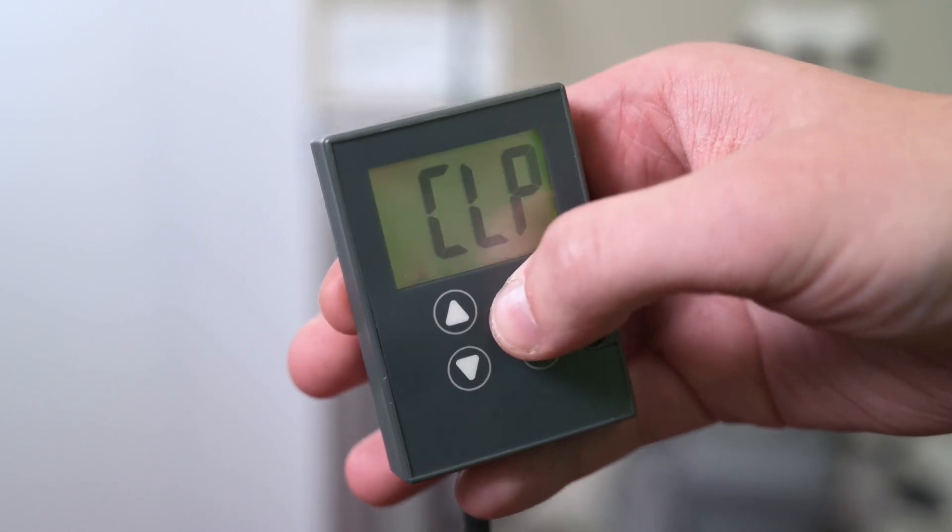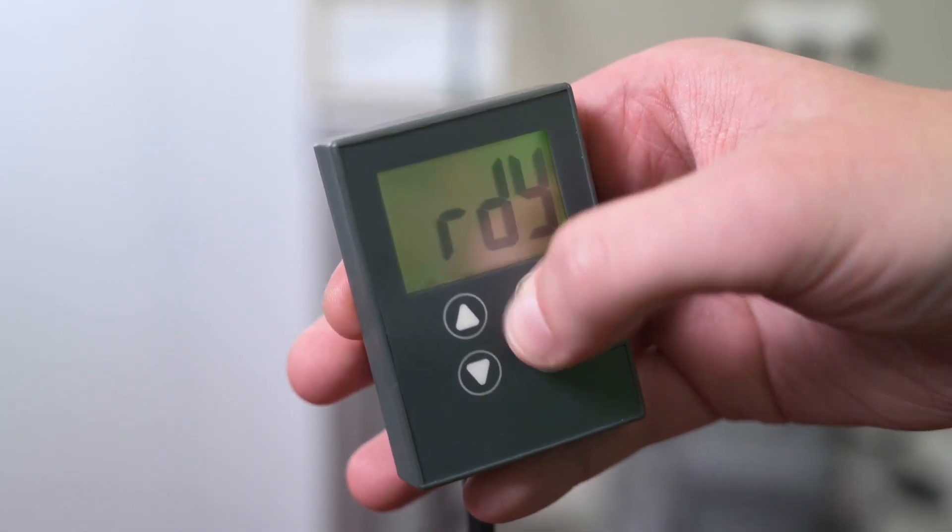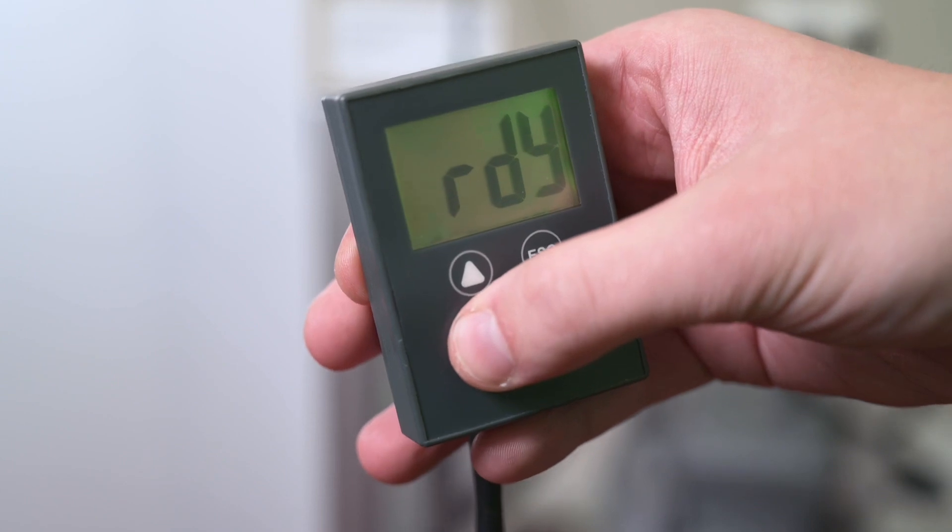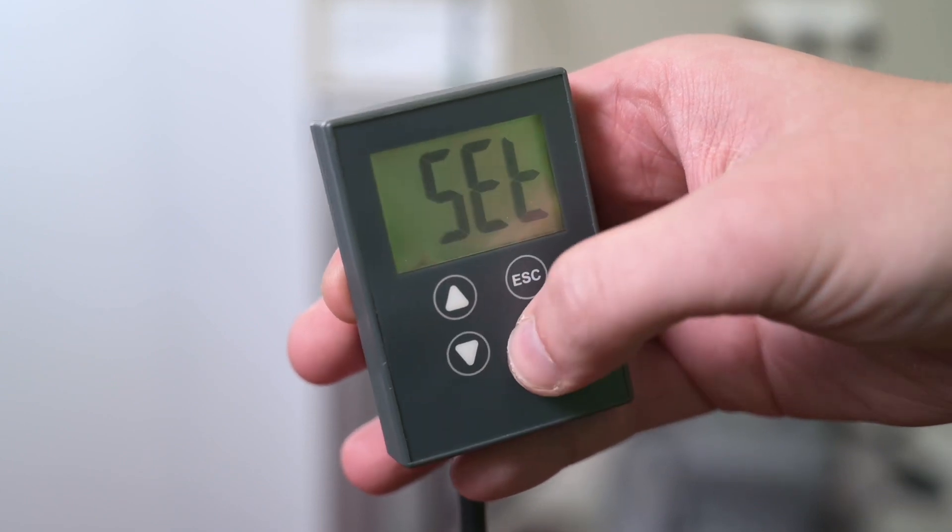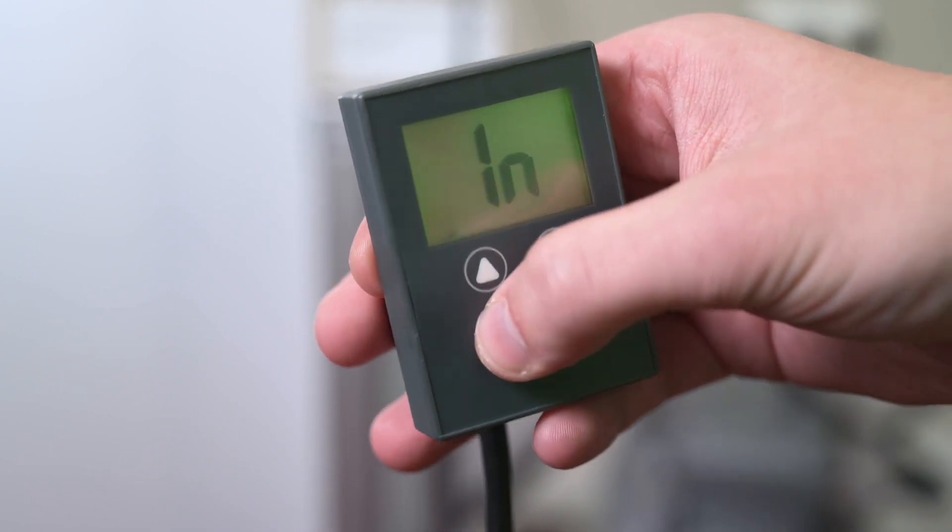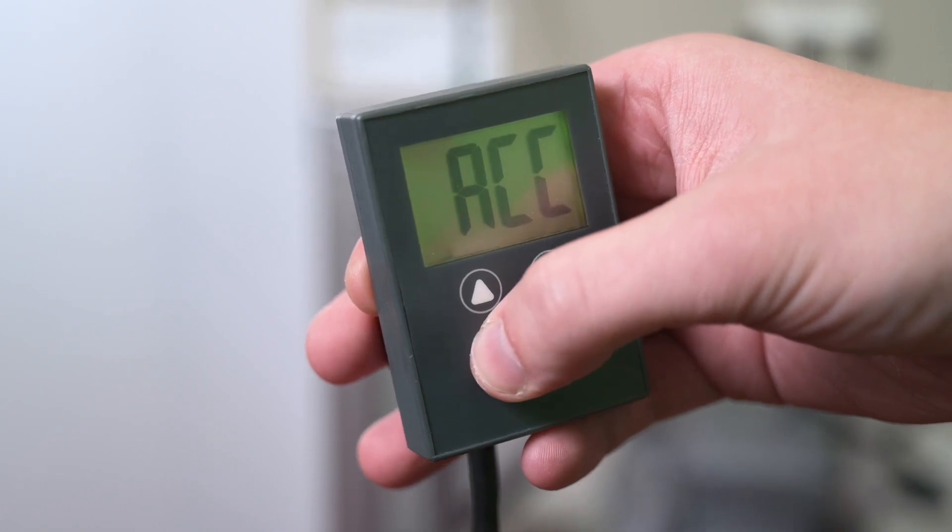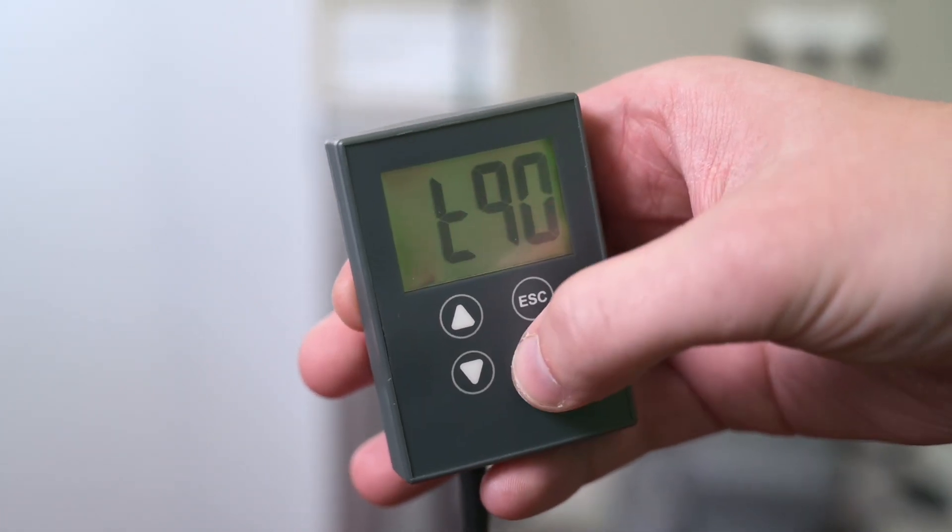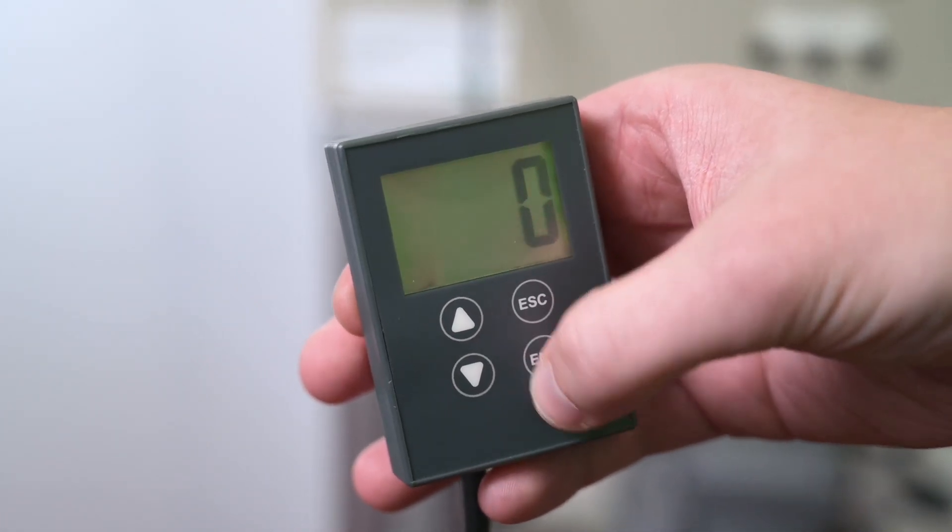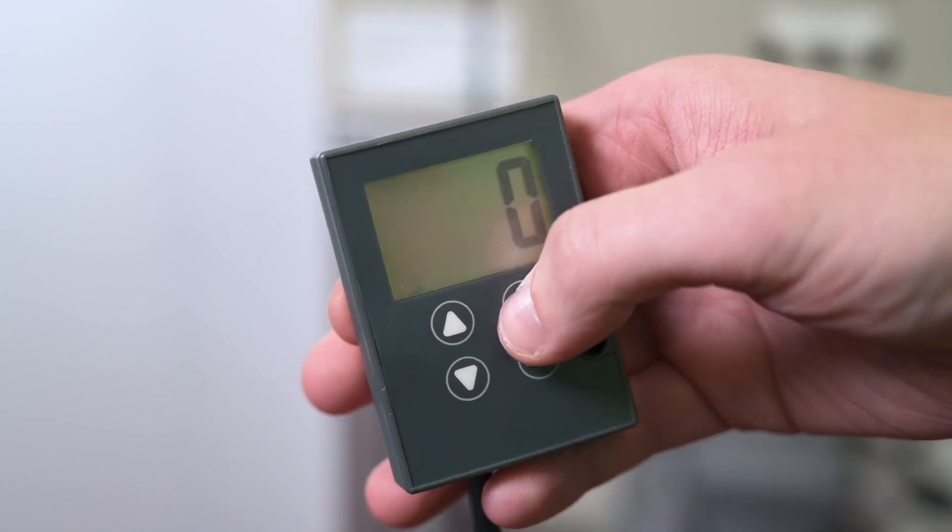Now we can manage the torque control CLP of the motor. Then, TQ0 parameter allows us to define the initial torque in the starting phases from 0 to 100% of the nominal torque. This is a boost to unblock the motor when it is stuck due to the nature of the process.